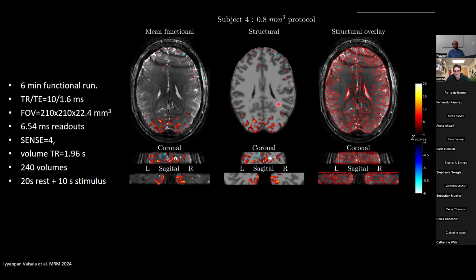Yeah. So most of the time, the problem is you have to shim your imaging volume. So most of the time is spent on shimming, trying to see where the bandings are, and then trying to shim again, adjust your volume. So more or less the first 20 minutes of acquisition is just going back and forth testing the sequence. We can't have an accelerated online reconstruction, so it's a basic Gadgetron reconstruction. So reconstruct, see the bandings, adjust volume, do that again. Cool, yeah, makes sense. Yeah, to focus on B0 more. Yeah. So pressing issues first.